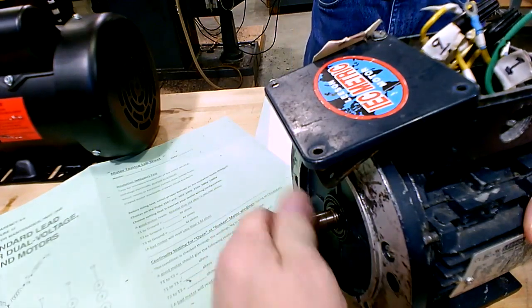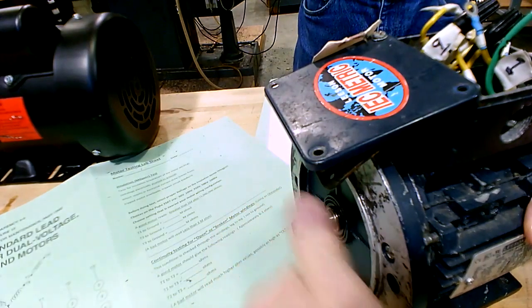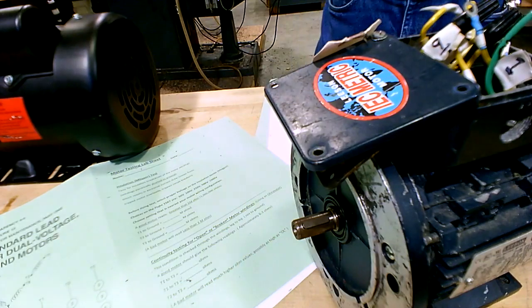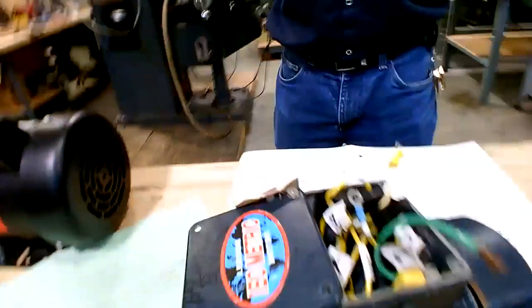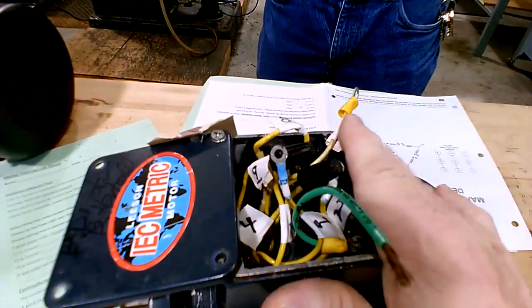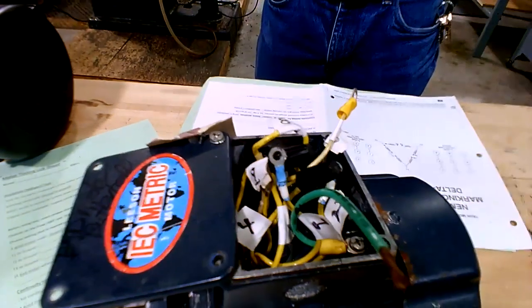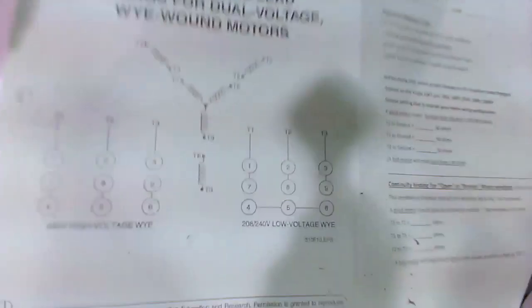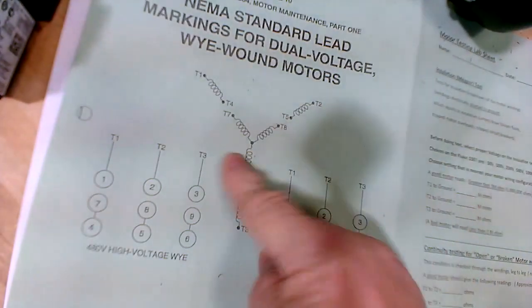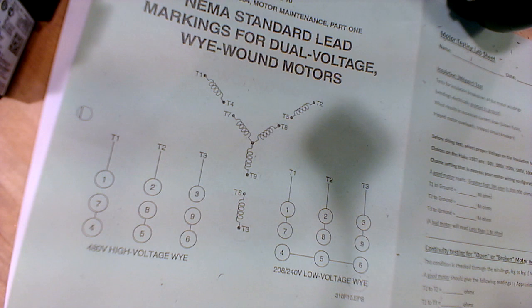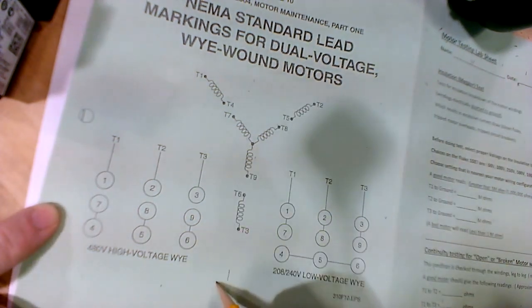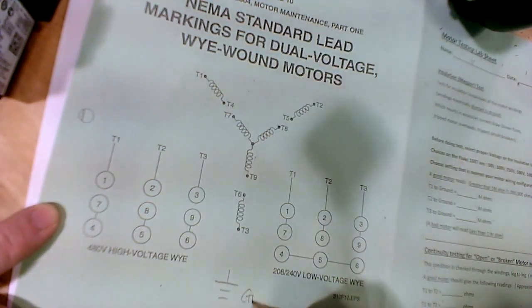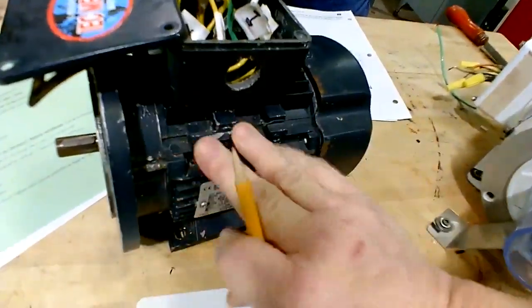Well, the bearings could go bad, it can lock up, right? You can actually feel that if it's obviously locked up. So that's a physical thing that can happen there. Then you can have an issue with the windings in there, where a winding could do two things. You can have a winding that can short to ground. Let's just draw the ground in there. You can have a winding that can short to the ground symbol, which would be the frame of the motor. So the frame of the motor would be grounded, okay?